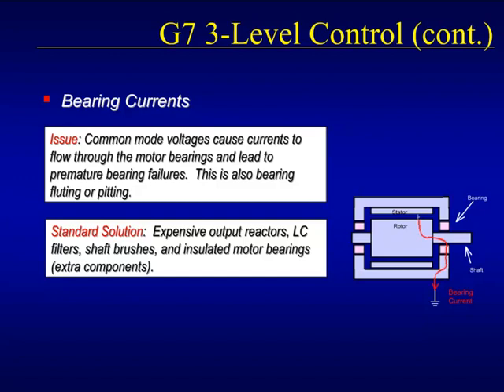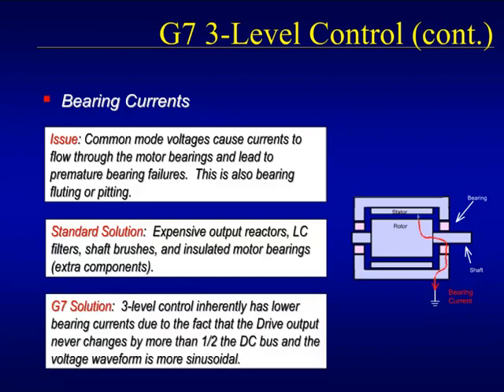Currently, the only solutions to the problem of bearing currents involve costly output filters or customized motor construction. The G7, with its 3-level output, reduces the chances of bearing currents by limiting the common mode voltages in the motor. Hence, no extra equipment or expensive motor construction is necessary.